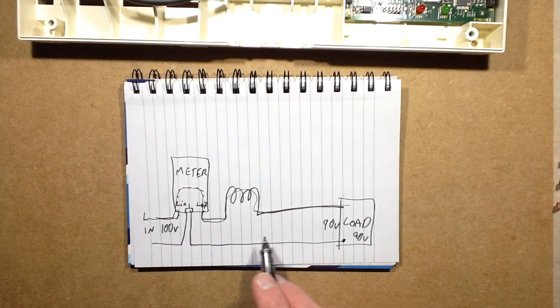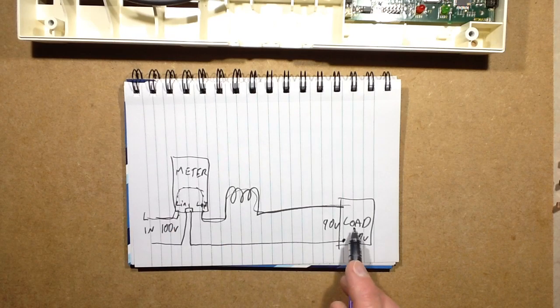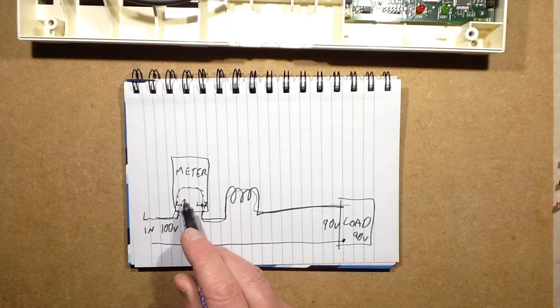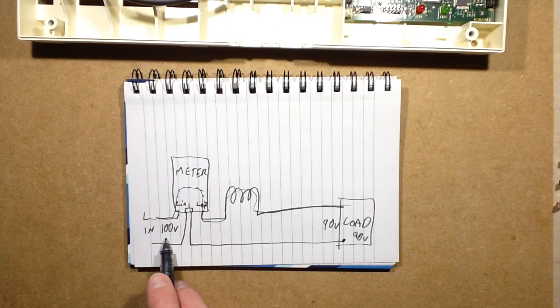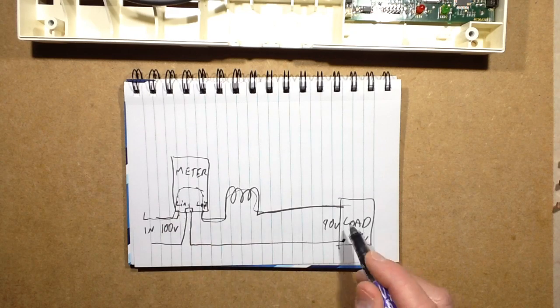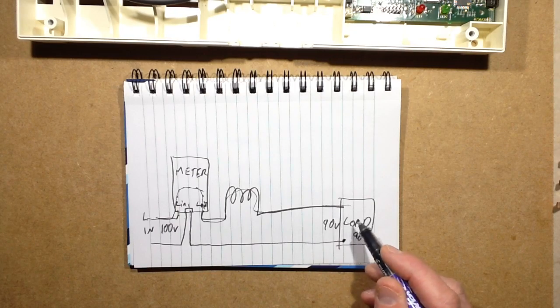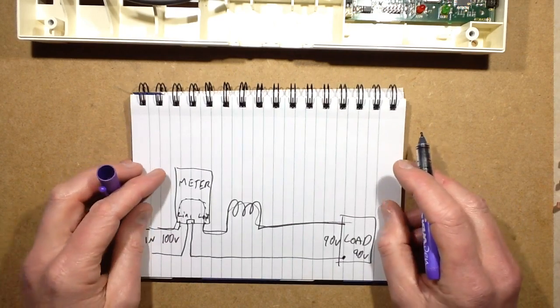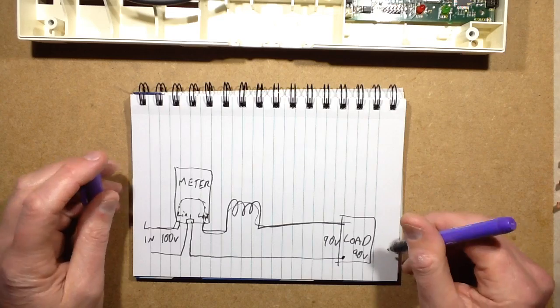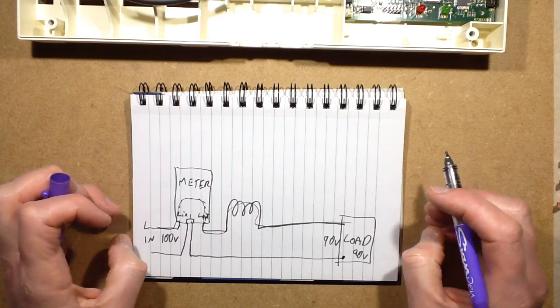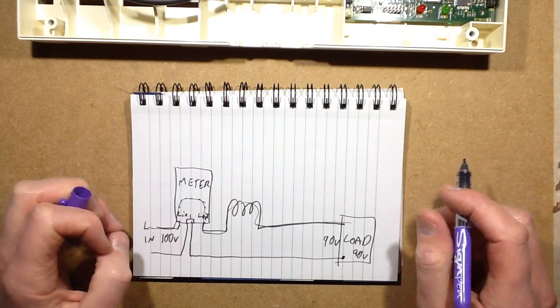So the meter's actually going to see a higher current being drawn by that machine, but it's also going to see it referenced to the 100 volts that it was measuring at the mains incoming supply, and that's how it will meter it. So that's actually going to cost more for the electronics loads, and that's also going to apply to things like LED lamps with the little switching power supplies. They're aiming to put out 3 watts regardless.